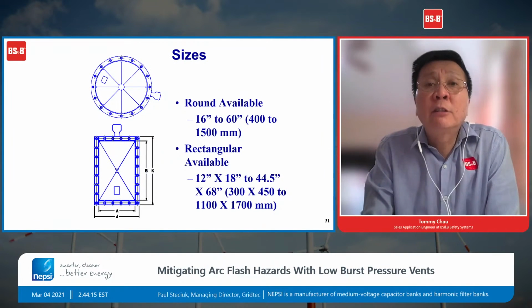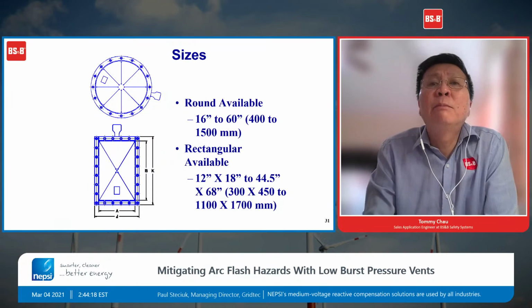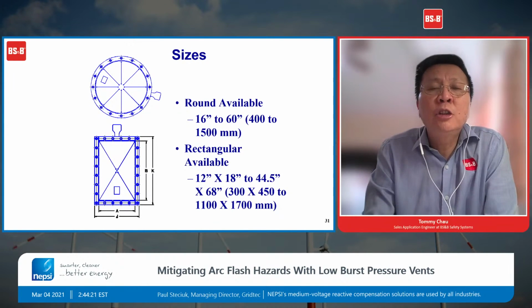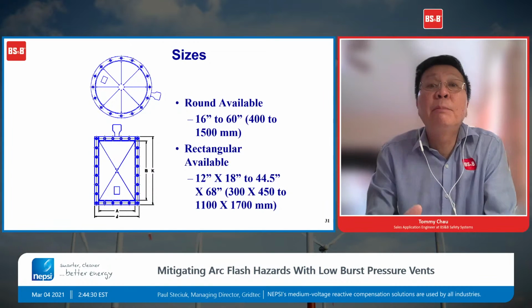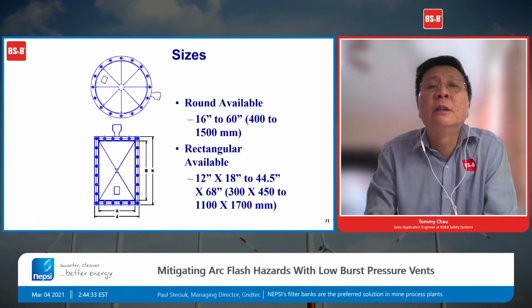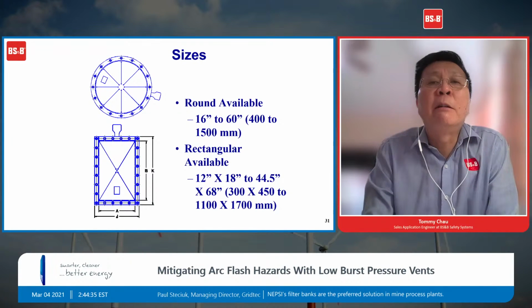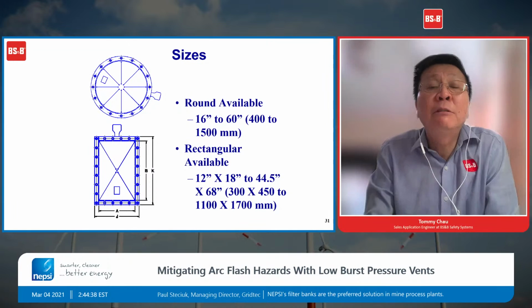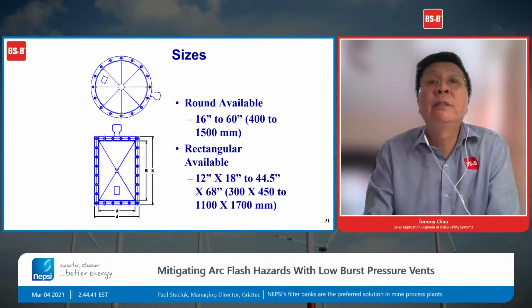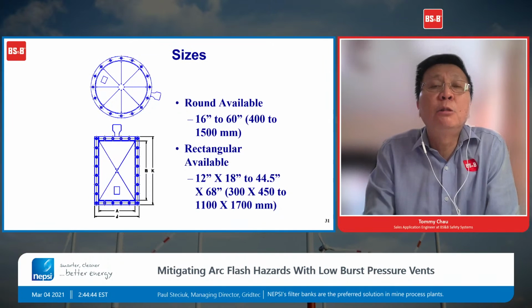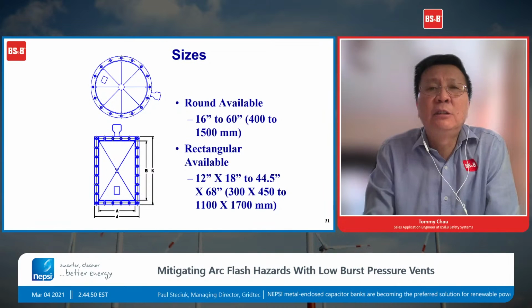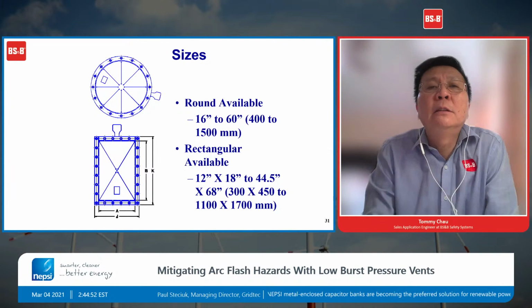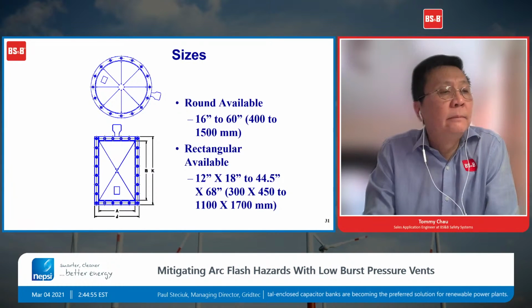Okay, so we manufacture different sizes, 16 inch up to 60 inch on the circular shape. We have rectangular explosion vents, 12 by 18 all the way up to 44.5 by 68. Please keep in mind these are the internal dimension opening area. So on the 12 by 18 inch panel, if you're using a 2 by 2 angle, the outer dimension would be 16 by 22 on a 12 by 18 inch inner dimension explosion vent.